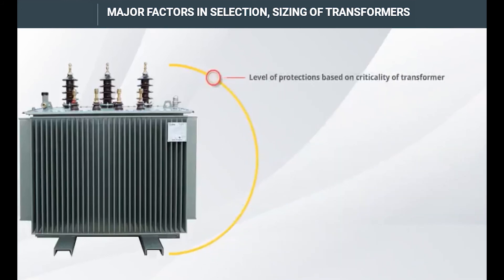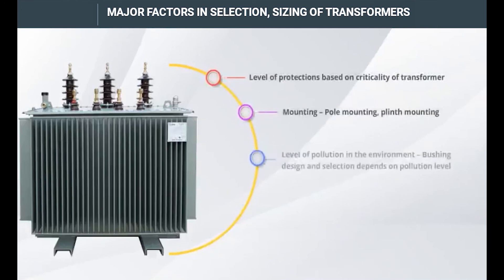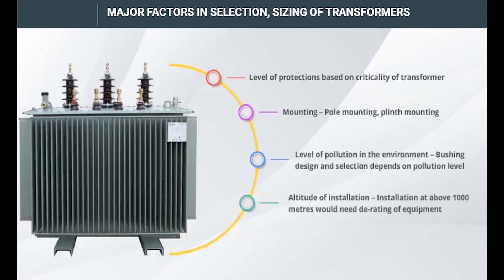The level of protection required depends on the criticality of the transformer. Mounting options include pole mounting and plinth mounting. The level of pollution in the environment affects bushing design and selection. Finally, the altitude of installation matters — installations above 1000 meters require derating of equipment.